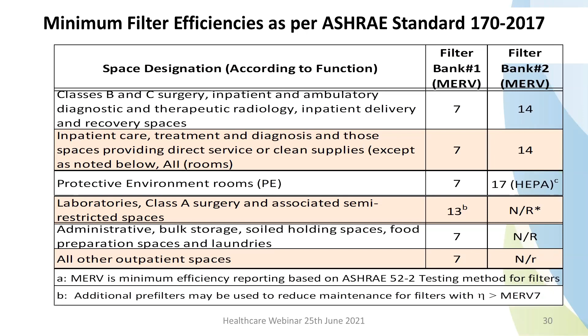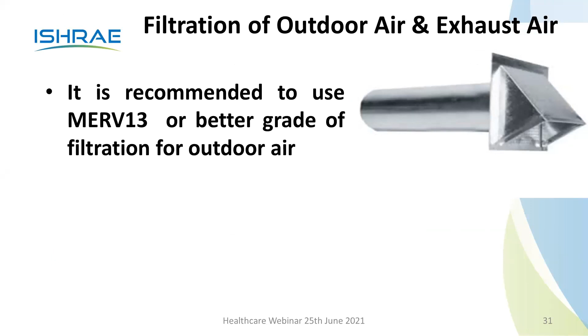Then the other point is filtration of outdoor air and exhaust air. It is recommended to use MERV 13 or better grade of filtration for outdoor air. The exhaust air must be protected for containment by at least MERV 10 grade filters. You can't just throw exhaust air directly outside. That's another important point.